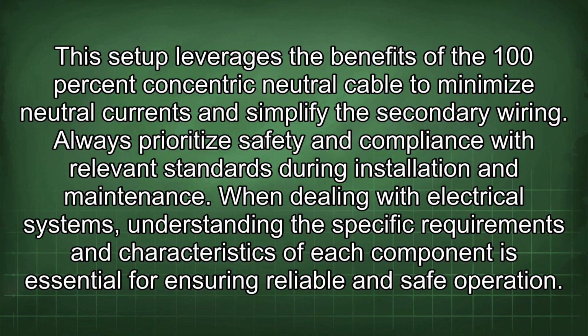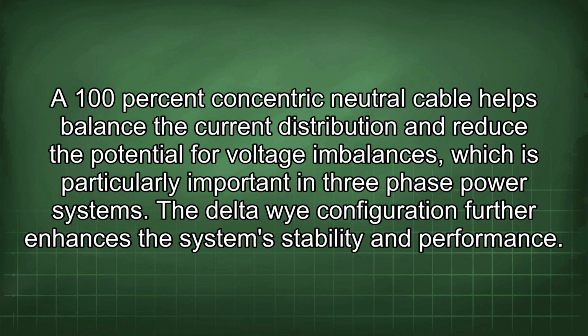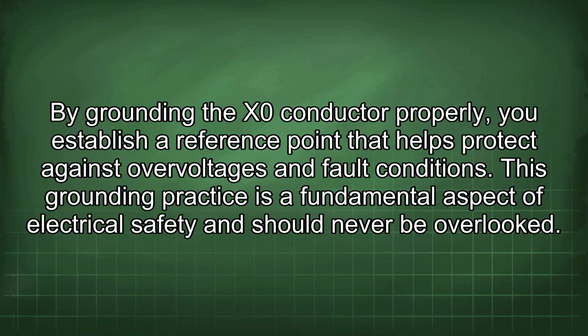When dealing with electrical systems, understanding the specific requirements and characteristics of each component is essential for ensuring reliable and safe operation. A 100% concentric neutral cable helps balance the current distribution and reduce the potential for voltage imbalances, which is particularly important in 3-phase power systems. The Delta-Wye configuration further enhances the system's stability and performance. By grounding the X0 conductor properly, you establish a reference point that helps protect against overvoltages and fault conditions. This grounding practice is a fundamental aspect of electrical safety and should never be overlooked.